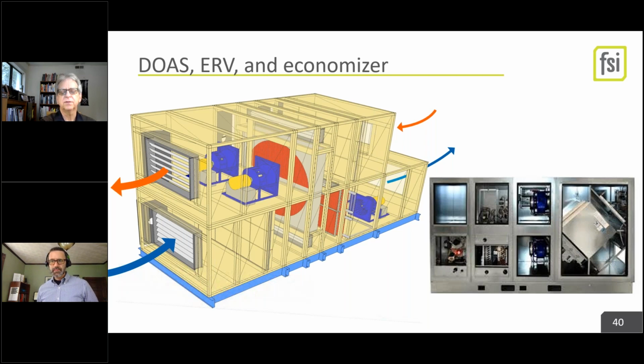So, Ben, if say this is a big high school or something, what's the physical scale of that drawing we're looking at? Yeah, so a lot of times you will divide up a building into wings and do a DOAS unit per wing. If I was doing a high school, I'd have a DOAS unit or two per wing. Let's say it's 3 wings, and then those would be the size of an SUV, give or take. I have also done DOAS units, I've commissioned them, for extremely large buildings, like a tall apartment building, and they're actually doing the heat recovery, which was rare until the current code.